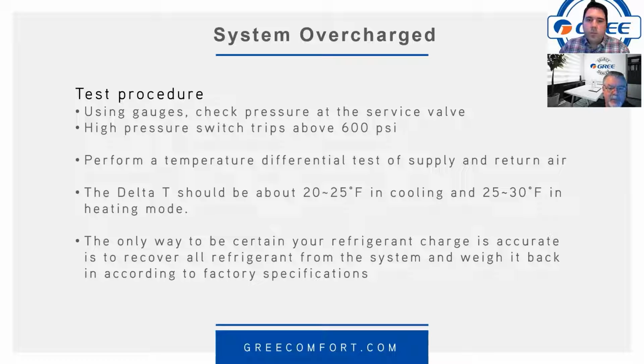But you can perform a temperature differential test of supply and return air. Delta T should be about 20 to 25 in cooling mode, 25 to 30 in heating mode, and you're trying to test as close to where the temperature sensor is, right? The ambient temperature sensor. Yes. So when you're performing your test, try to be as close to those as you can in cooling or heating mode: the return and supply as close to the actual return and the actual supply as you can get. Yeah.